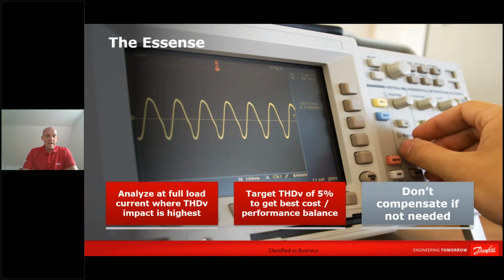Now, just to give you some guidelines to avoid having to do harmonic analysis on each and every installation that you're doing, I normally have a rule of thumb for when you need to do your calculations. First of all, you need to do your analysis at full loading, so the highest loading, where you see the highest impact on the voltage. You should try to reduce the voltage distortion to less than 5%. That's good engineering practice, and that's where you get the best cost performance balance. And you should not start compensating if it's not needed, simply because it's a lot of money wasted that way. And maybe I can give you a guideline for when to do it.